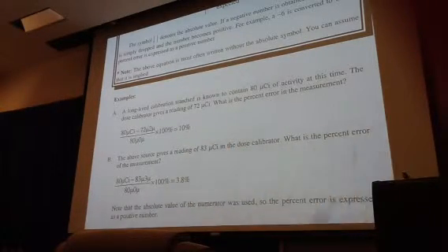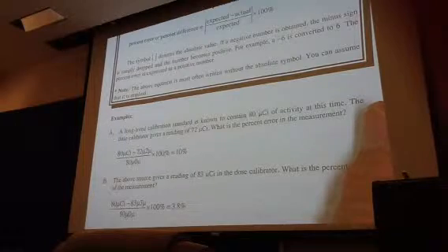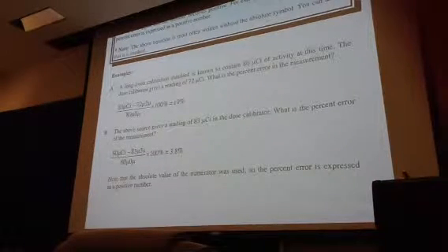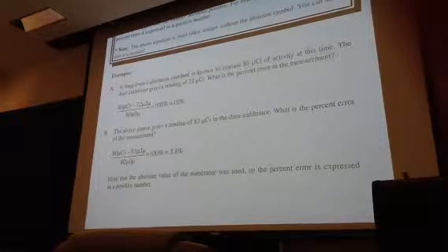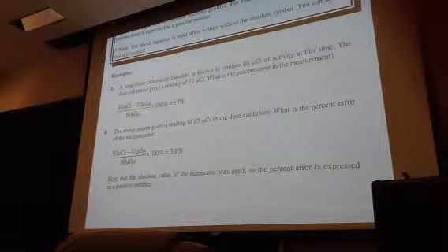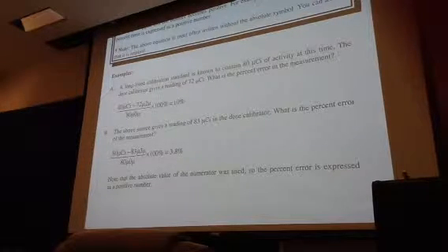Okay? So it can't be used, so the machine has to be recalibrated, or cannot be used at all? It has to be repaired. Either repaired or replaced, if you can't fix it. Usually, what you have to keep in mind is that we have that electrical source going to the gas, especially in your dose calibrator or in your survey meters. Sometimes the battery that's supplying that is going out. If you have a Capintec dose calibrator, some of those have a voltage check that you have to use before you operate the equipment. It should read like 122 volts. So you do that first, then you do a background check, then you do your measurement of your constancy sources.